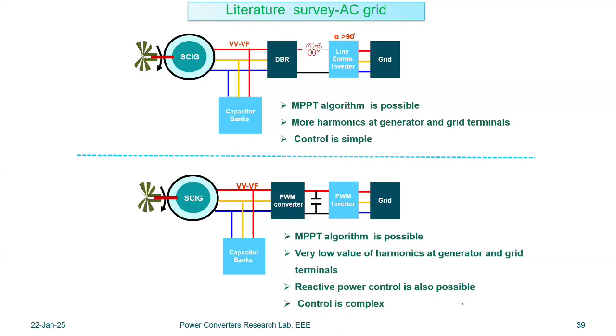Otherwise, for those who want to improve the power quality aspects, instead of a diode bridge and line commutated converter, we can go with a PWM converter and a PWM inverter connected to the grid. Then MPPT is also possible, with very low harmonics generated at the grid terminal. Reactive power control is also possible, and the control is also complex.